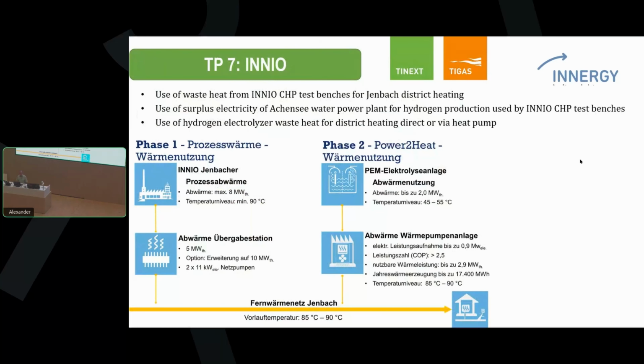In sub-project 7 in Jenbach, as I showed, there is the idea to use waste heat from CHP test benches they have in the company. These are quite big machines, so we are talking about several hundred kilowatts. Each machine which is produced is first tested and then delivered. Of course they produce a lot of waste heat, and this can be used in the district heating system.